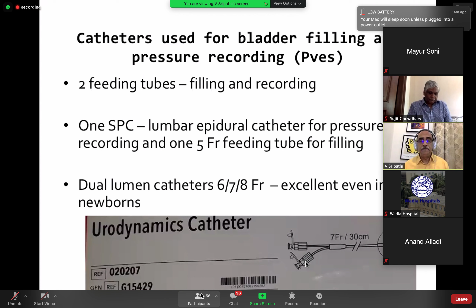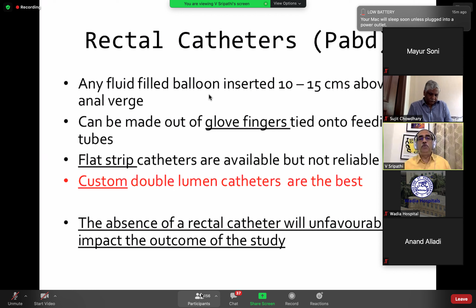So you can use 2 feeding tubes, but we use these custom-made urodynamic catheters, which are double lumen catheters, and they're pretty good. Again, rectal catheters: I cannot emphasize the importance of rectal catheters. You can do a study without a rectal catheter, but if you want to publish the results of your urodynamic studies later on, you will find that generally you can't get a very good opinion unless you put a rectal catheter which subtracts abdominal pressure. Again, we use a custom catheter, but you can use any fluid-filled balloon tied onto a feeding tube.